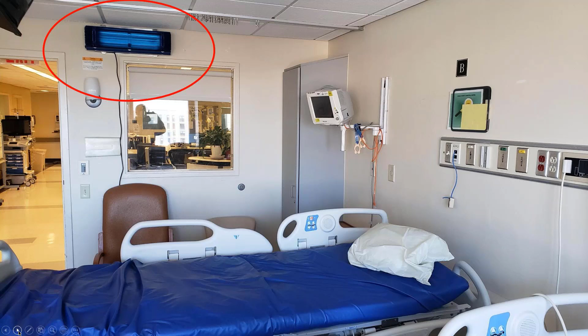They could be in lobbies too — especially in hospitals, where they're triaging people or people are coming into the emergency room, just trying to keep that air disinfected. A hospital room has 6 air changes per hour, meaning every 10 minutes that air flushes out of the room, past these lights, and into the air handling unit.